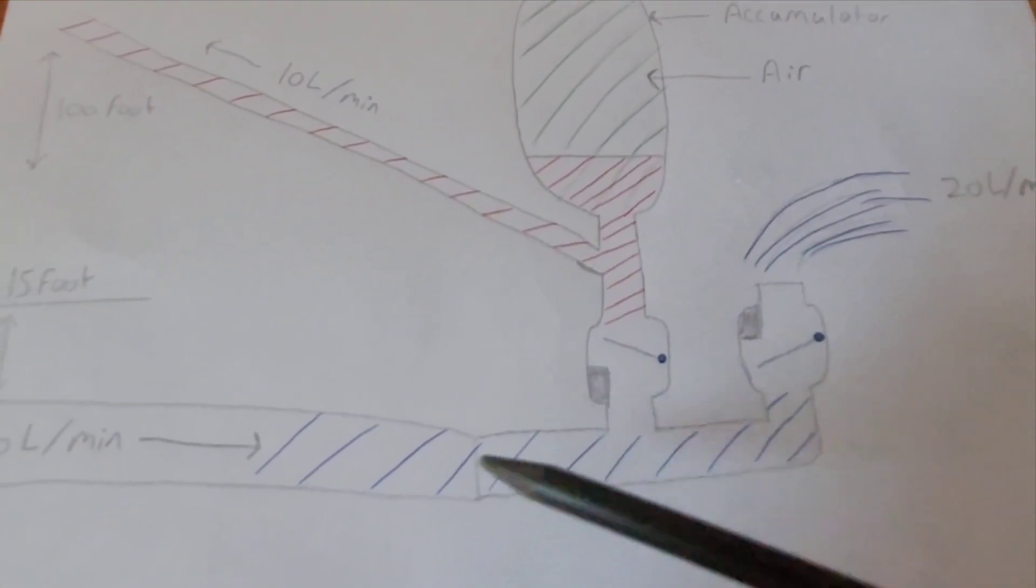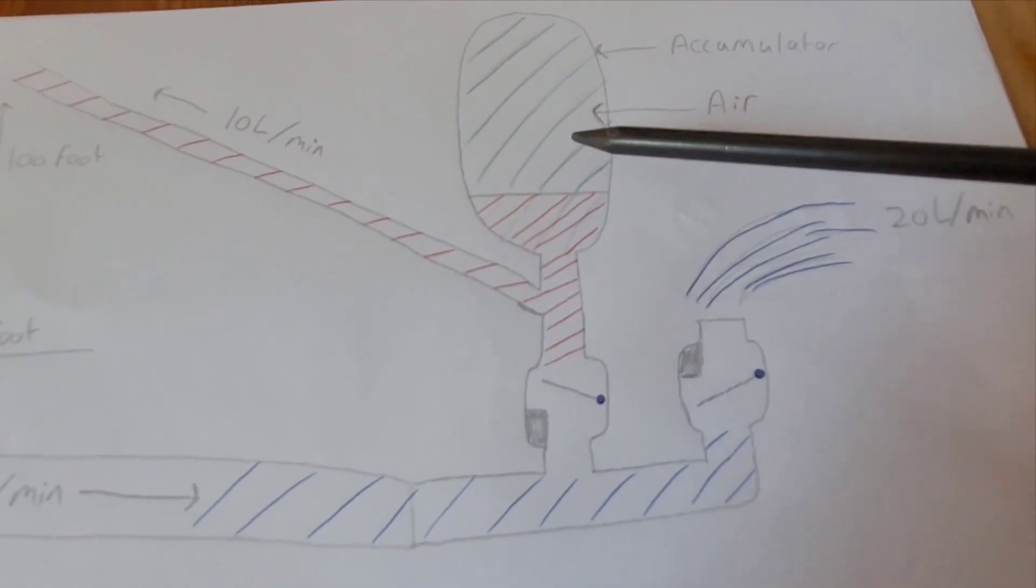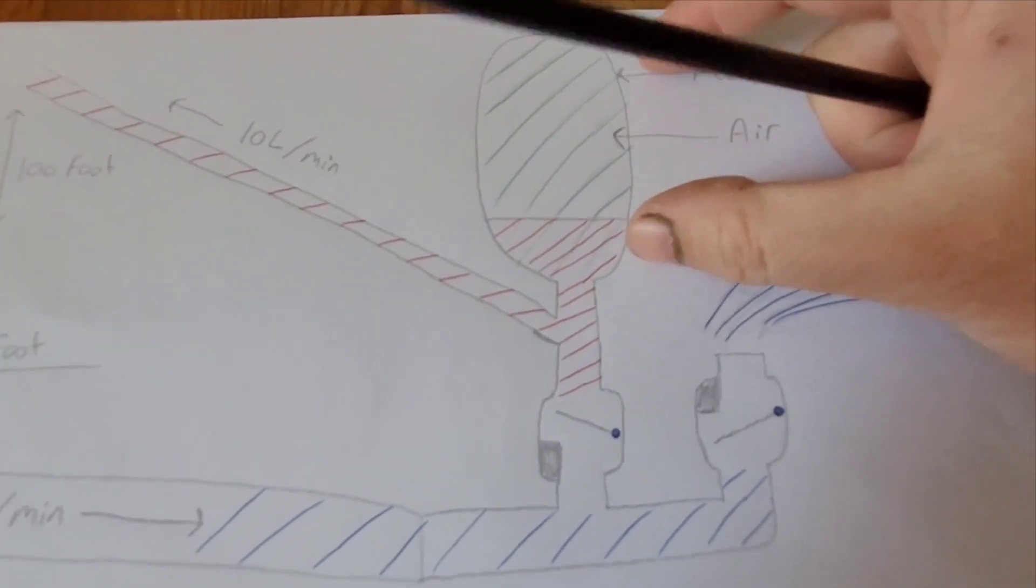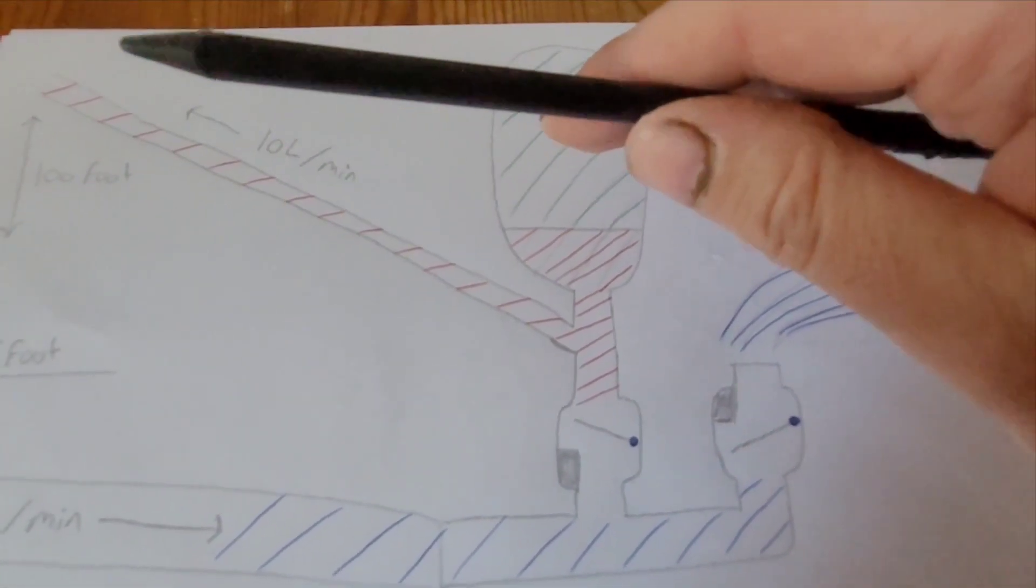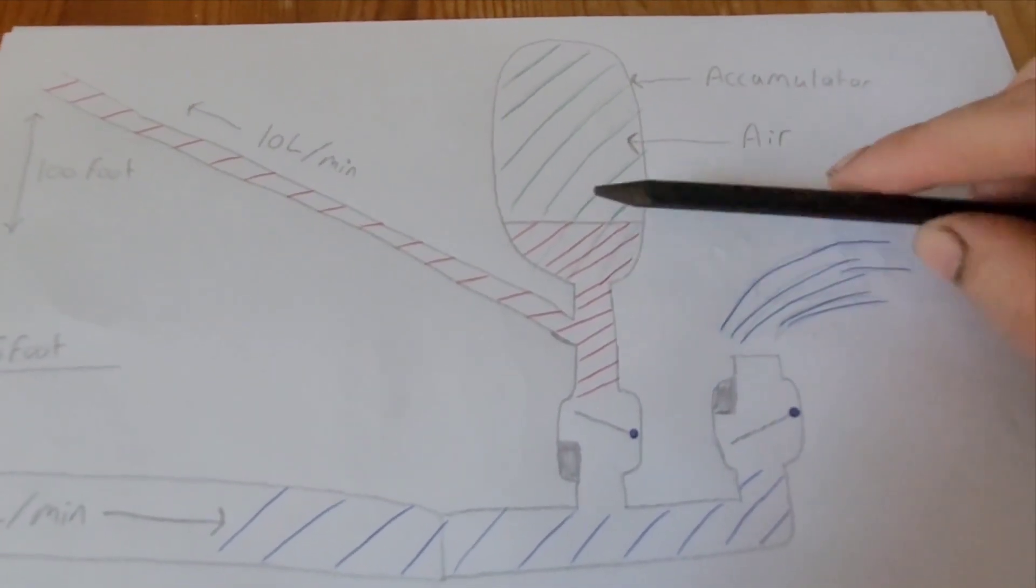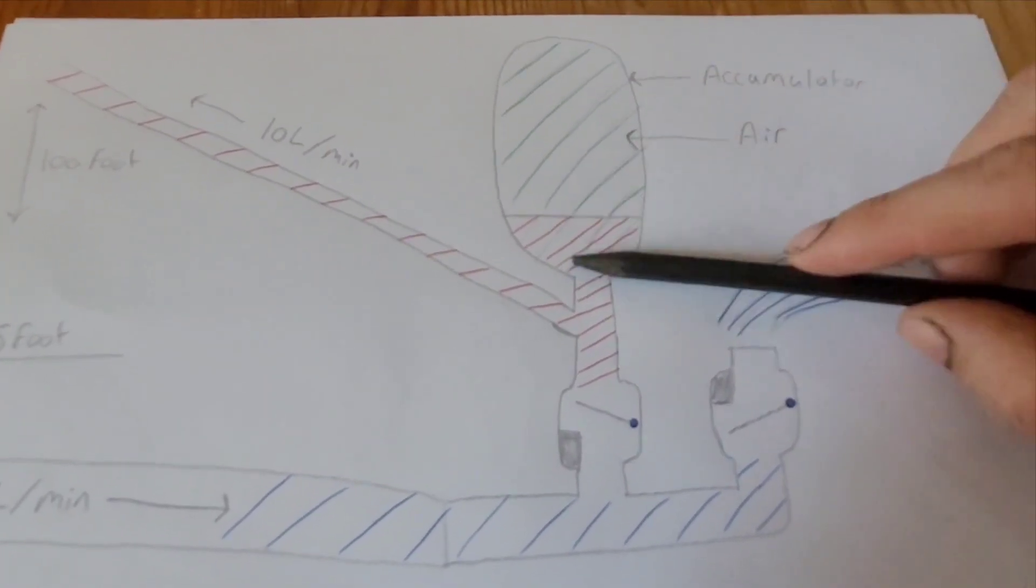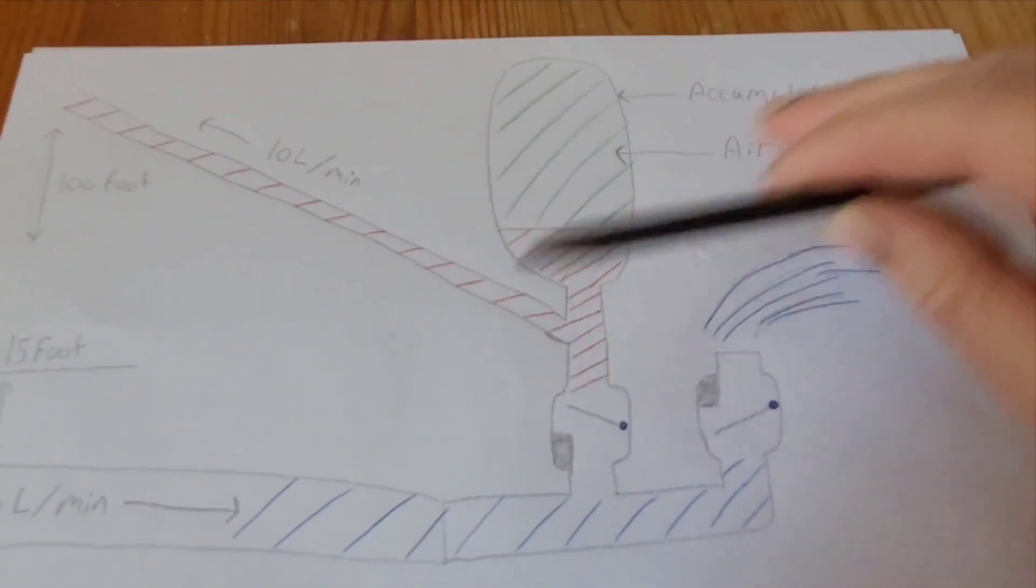So that's how that works, so it's the rushing water that actually makes it pump. And then you have accumulator in the air chamber, so it's full of air now, and this will go up. And this will actually, because liquid, you can't compress the liquid, that's why you use hydraulics, but it won't compress, but air you can compress it or any gas. So, this air now, as this goes bang up, this air will flex a bit, and it'll take out that sort of shock, and it'll keep a constant sort of pressure.